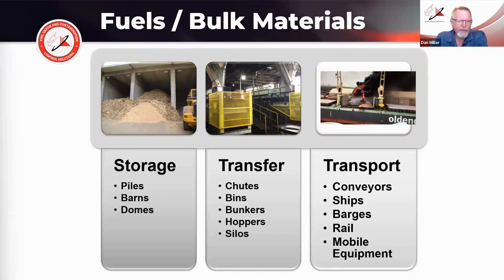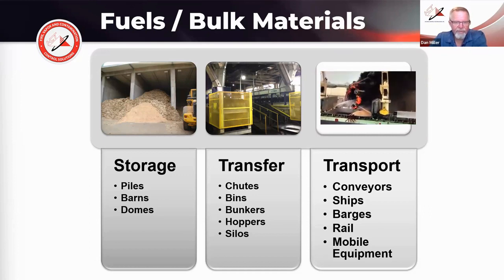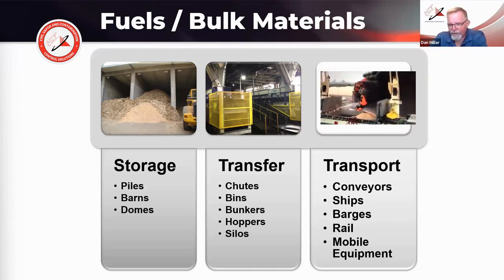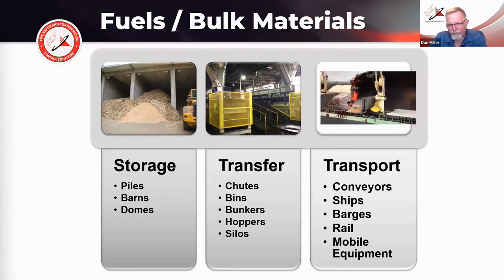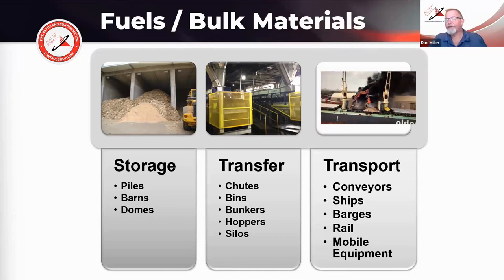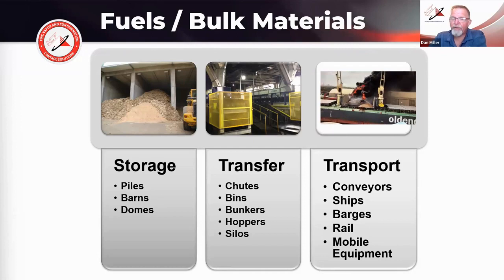Transfer areas, chutes, bins, hoppers, and silos are where the coal, biomass, or whatever the fuel is, gets moved around. From those you get fugitive dust that settles and enters void spaces under belts and begins to smolder, or you get float dust, which is easily aerosolized, floats, and lands on beams and things above your head and shoulders and builds up.